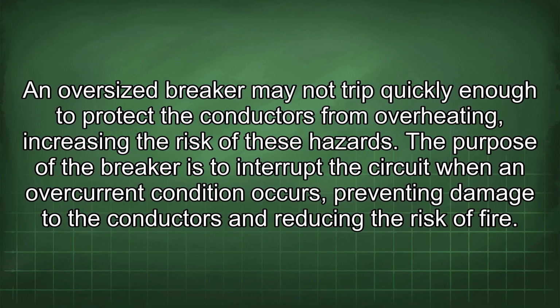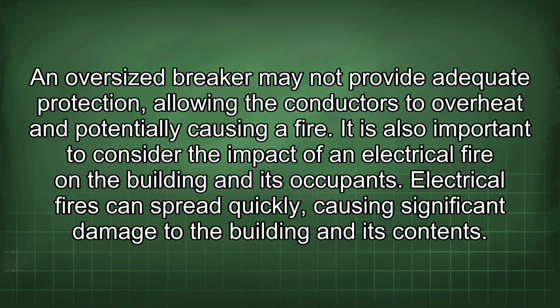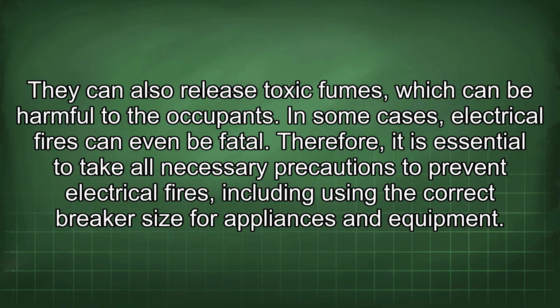The purpose of the breaker is to interrupt the circuit when an overcurrent condition occurs, preventing damage to the conductors and reducing the risk of fire. An oversized breaker may not provide adequate protection, allowing the conductors to overheat and potentially causing a fire. It is also important to consider the impact of an electrical fire on the building and its occupants. Electrical fires can spread quickly, causing significant damage to the building and its contents. They can also release toxic fumes, which can be harmful to the occupants. In some cases, electrical fires can even be fatal. Therefore, it is essential to take all necessary precautions to prevent electrical fires, including using the correct breaker size for appliances and equipment.